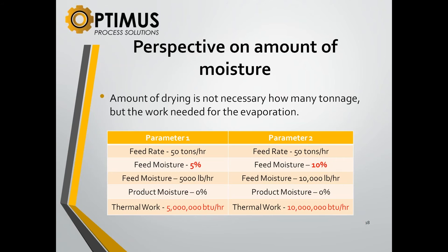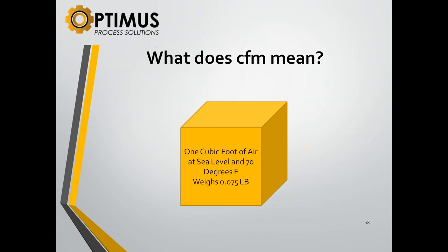And then think through that, because with 5%, 10%, you can really get screwed up if you're using, say, 1%, 2% versus 10%. That changes a lot. If you say 5 to 10%, we would have to design for 10%. If material is 4 or 5% most of the time, our dryer would be twice too large.